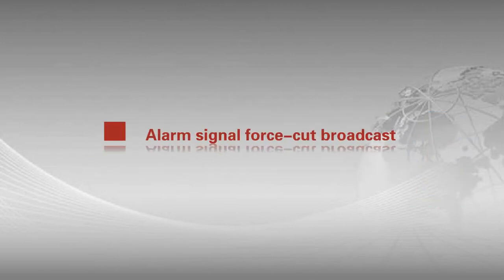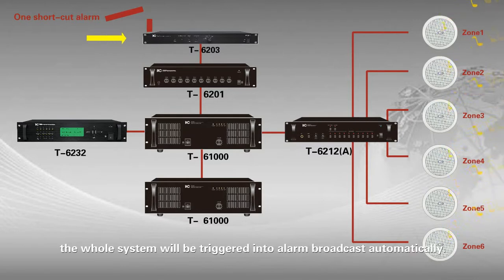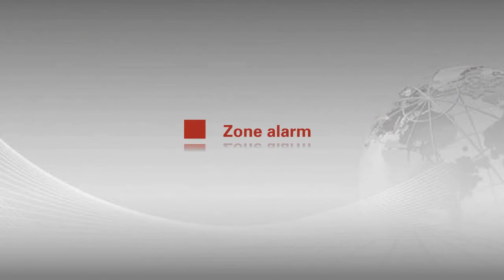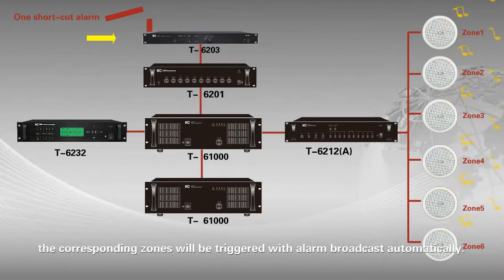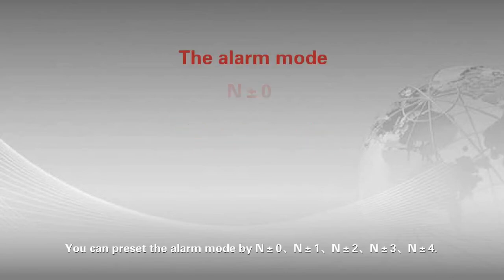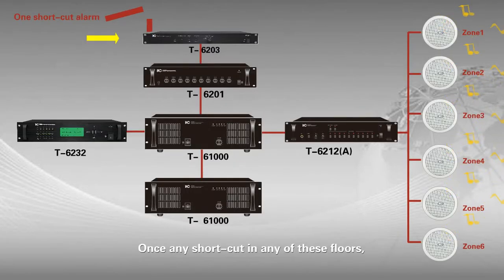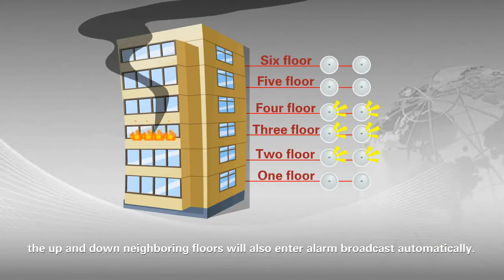Alarm signal priority broadcast. All-zone alarm: matching with the alarm generator, once there is a short-cut alarm the whole system is triggered into alarm broadcast automatically. Zone alarm: once there is a shortcut alarm, the corresponding zones trigger alarm broadcast automatically. Neighboring alarm: you can preset the alarm mode by N±0, N±1, N±2, N±3, N±4 — once any shortcut on any floor triggers, the up and down neighboring floors will also enter alarm broadcast automatically.